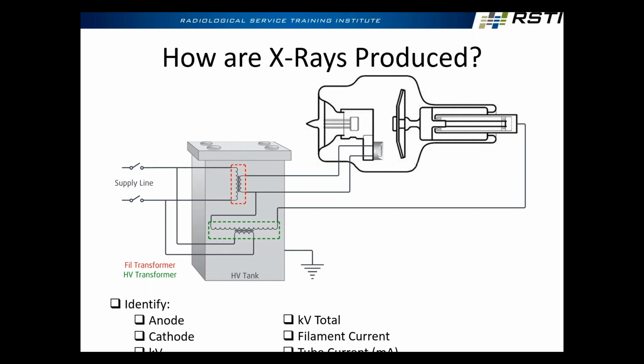But new ones, well, everything's inside the housing. So if we want to see the filaments glow, we actually have to remove the collimator, look in the port of the tube, all that good stuff. All right. This is all going to be supplied by our generator. Generator contains both our high voltage transformer down here and our filament transformer up here.